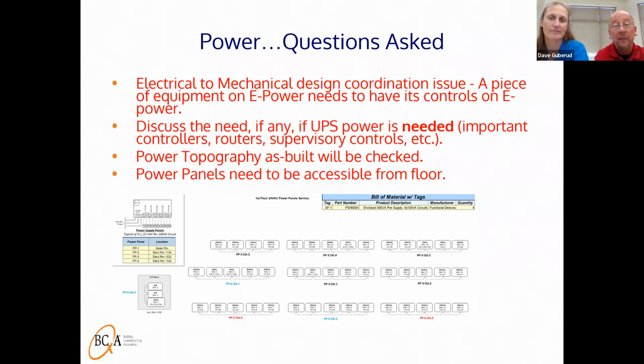And then the need potentially of UPSs. And the other thing that we're doing and telling our control contractors is that we will be checking, and we want to make sure that they're creating as-built conditions of how they're looping their power to devices and how they're looping the communication trunk. Because some application engineer is probably looking at a reasonable way of daisy chaining that, but field conditions might be different, so the wires get run differently, or maybe they actually put a repeater in there and they T-tapped off and branched. But we really want to make sure that they have an as-built, and we do that by working with them and by disconnecting the trunk to make sure what's downstream of that disconnection actually goes dead.